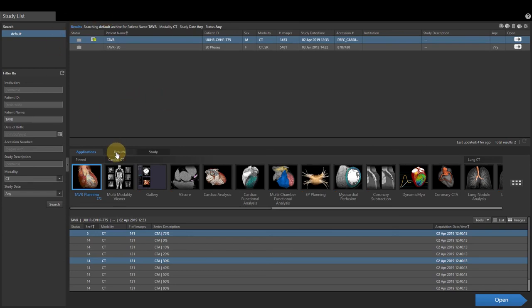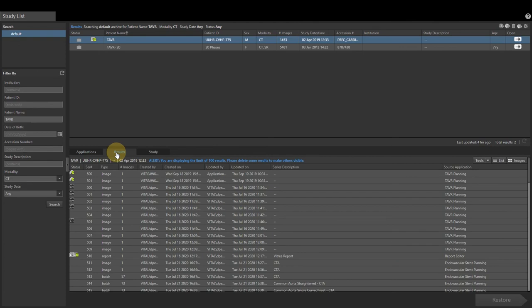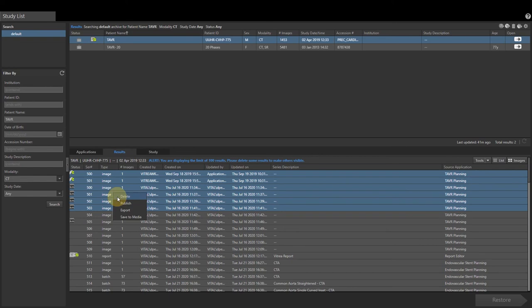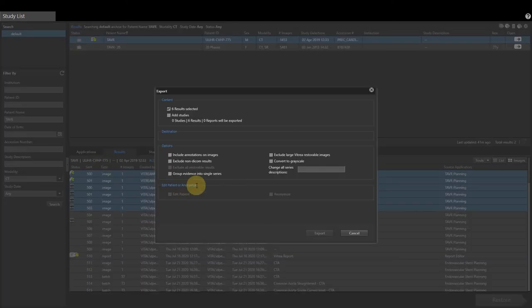From the Results tab, edit your snapshots as well as any reports by left-clicking and holding Control to select multiple items. Once selected, right-click and export to your DICOM destination.